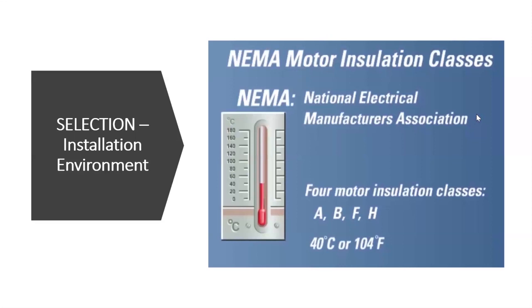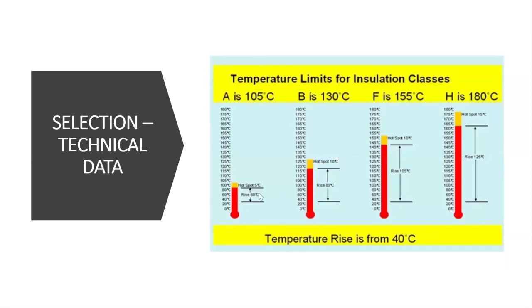You look at the insulation class of the motor. Per the NEMA standard, we have the 4 motor insulation class, the class A, B, F, and H, and all of them have their rate of temperature tolerance as seen over here. For an insulation class A motor, it can have a rise in temperature up to 60 degrees. So for an ambient temperature of 40 degrees, the motor can rise up to 60 degrees and has a hotspot of 5 degrees Celsius, after which the motor will fail.